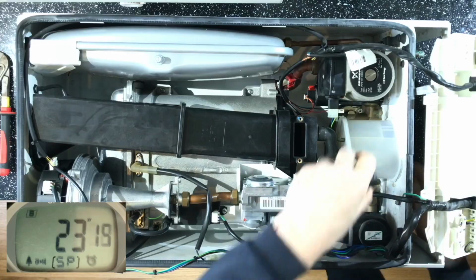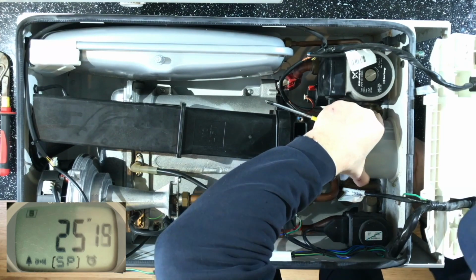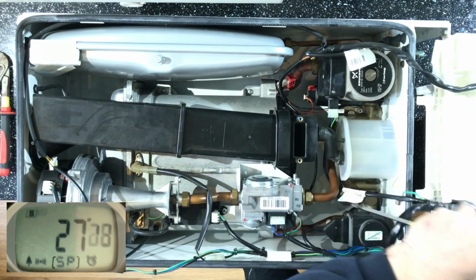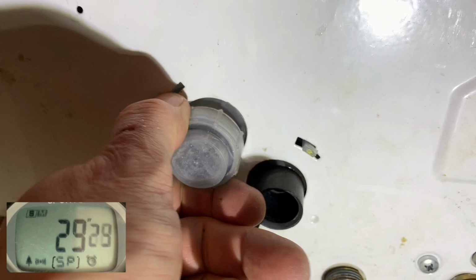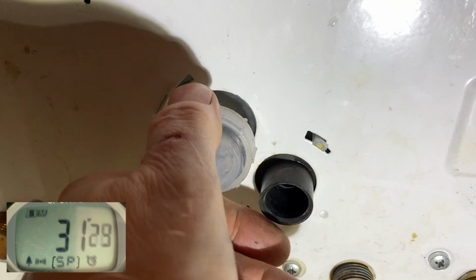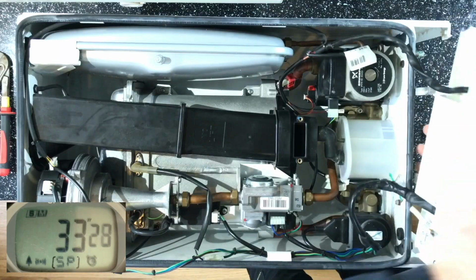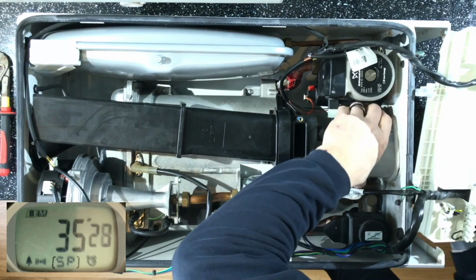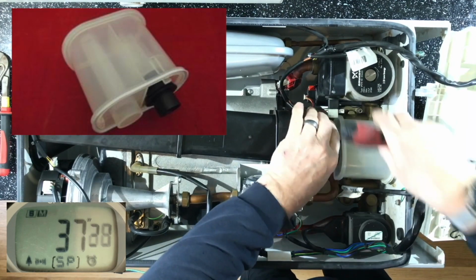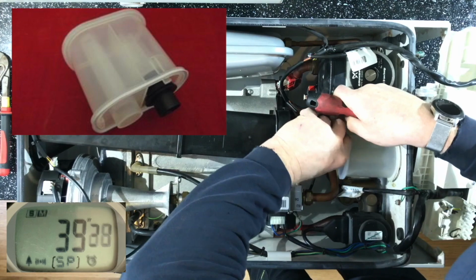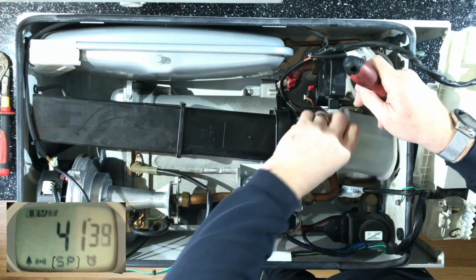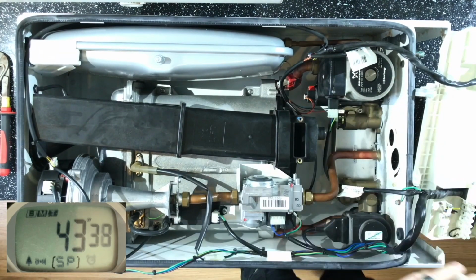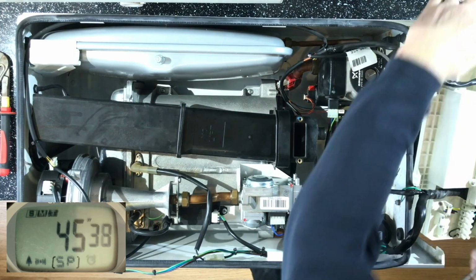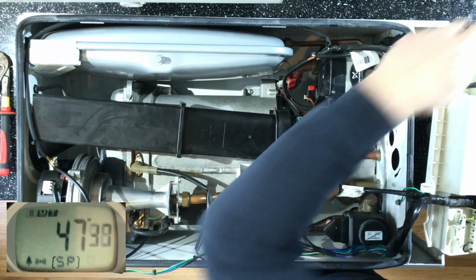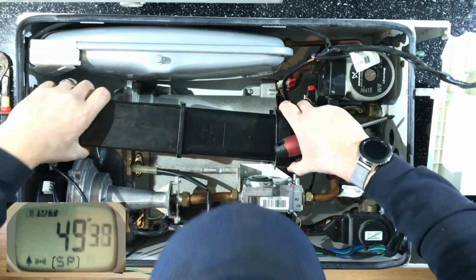The next thing I'm removing is the condensate trap. Now, this is one of the old traps, and it has a retaining nut on the bottom here, which I'm taking off, which holds the condensate trap in position. In the new ones this doesn't exist now; it's just a plastic cover which goes on, moulded into the trap itself. Now I've removed the trap, I can start taking off this manifold.